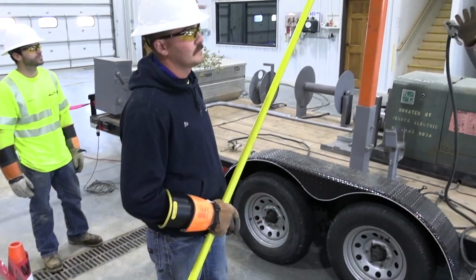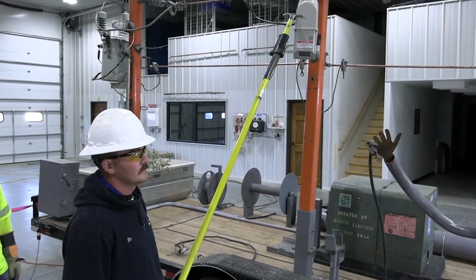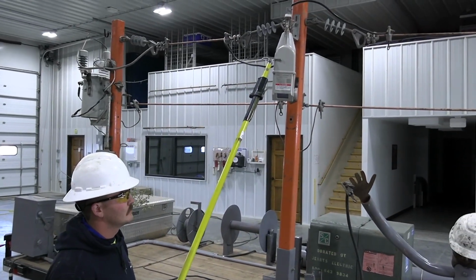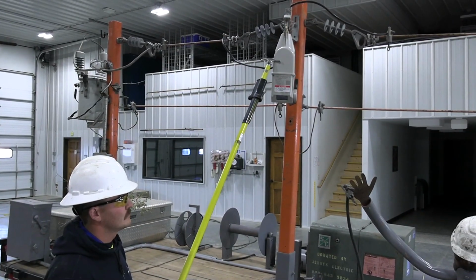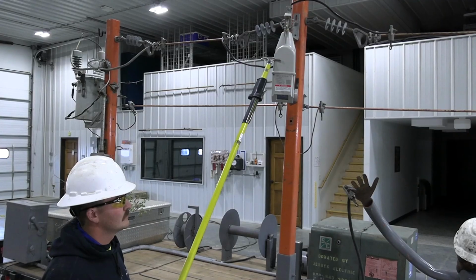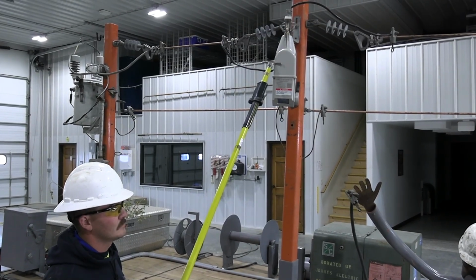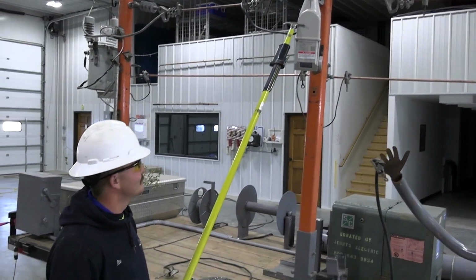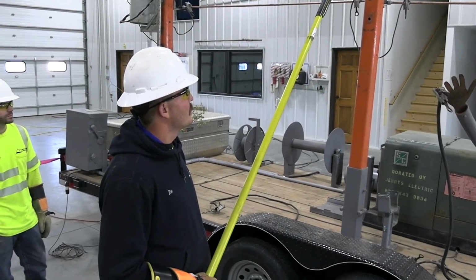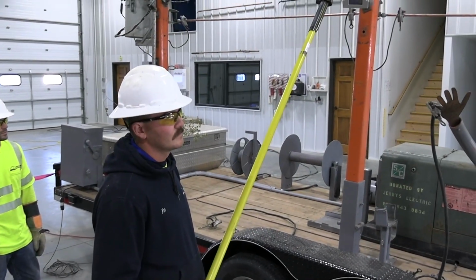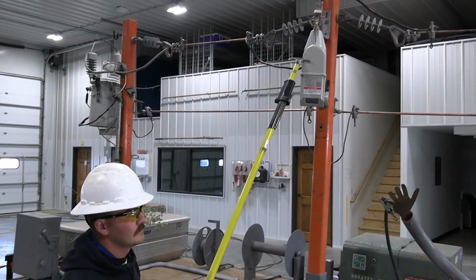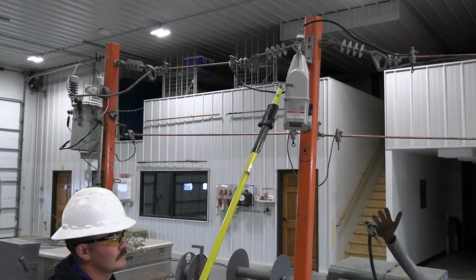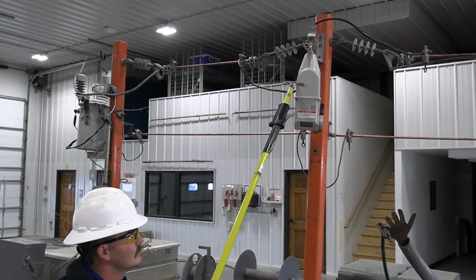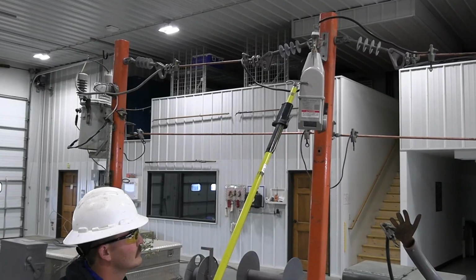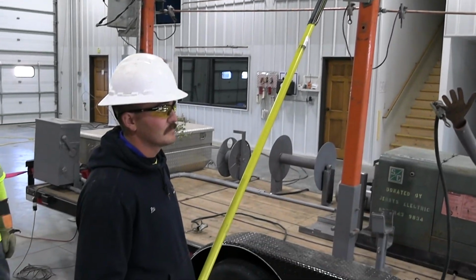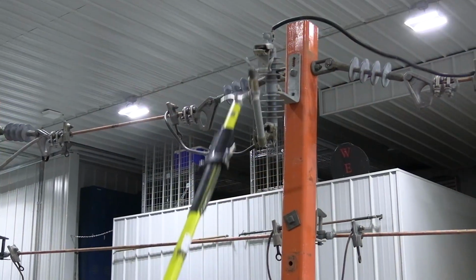Moving down the line is a vacuum recloser mounted on an overhead pole. It acts like a circuit breaker. If something were to come into contact with the line downstream, such as a broken tree limb, the device would open and stop the flow of electricity. This would activate 3 times, once every 2 seconds, until the fault clears, or after the third attempt, it would fall open until a line worker is dispatched to investigate the issue.